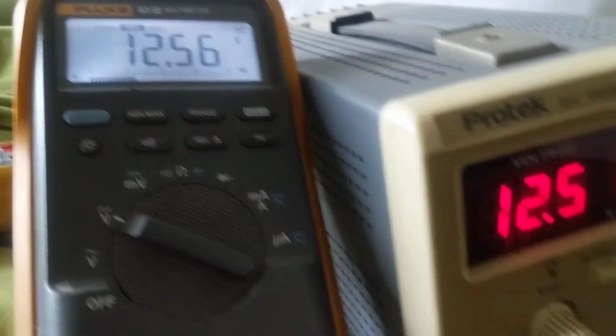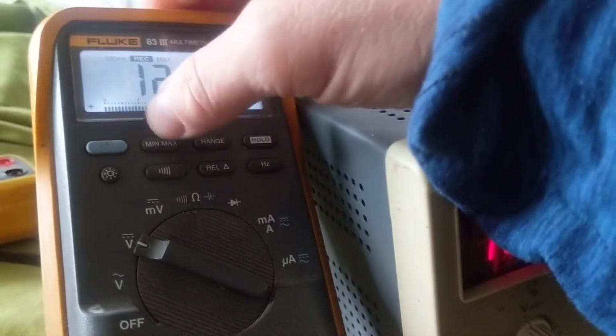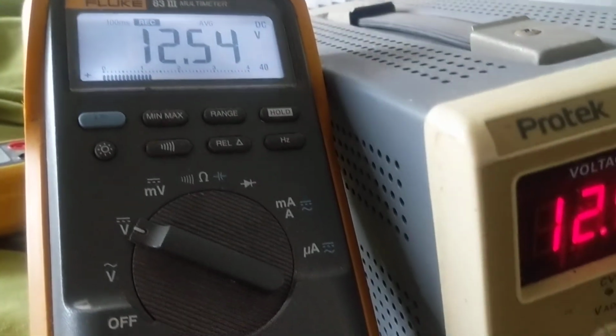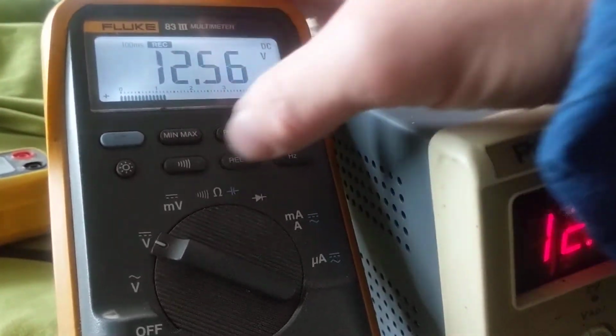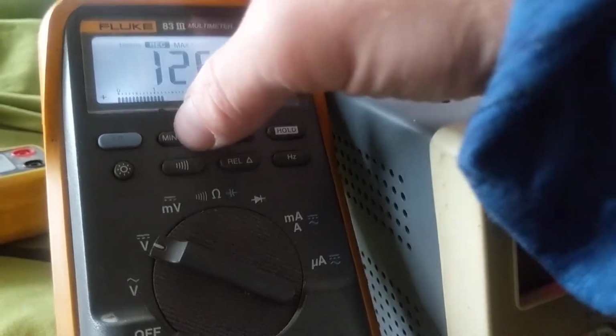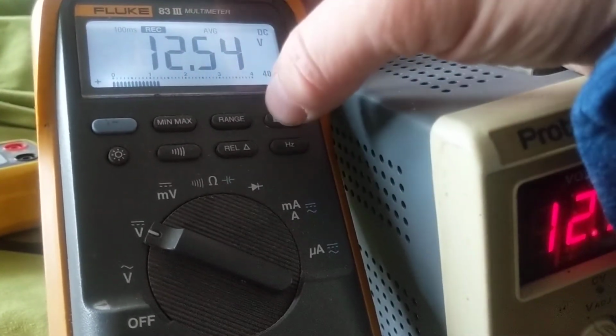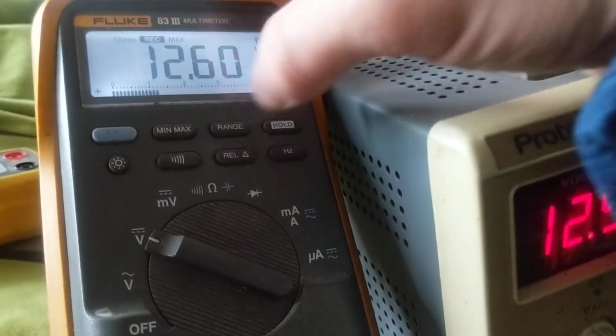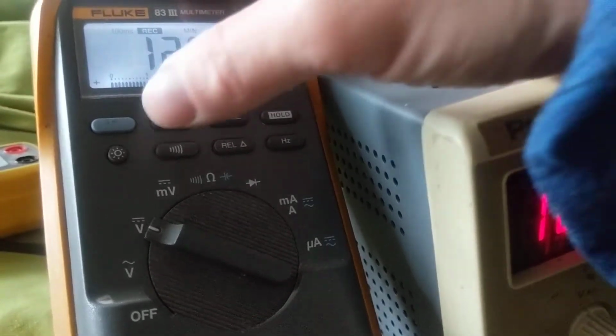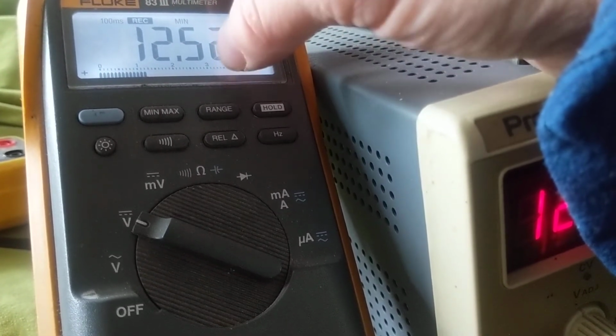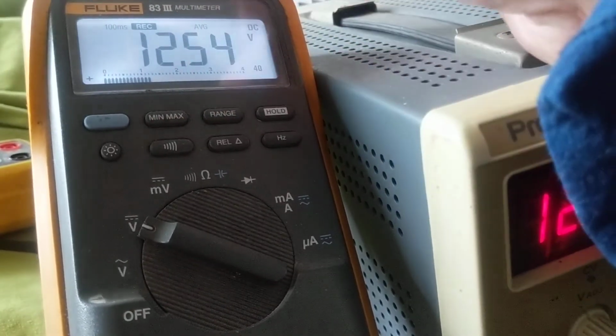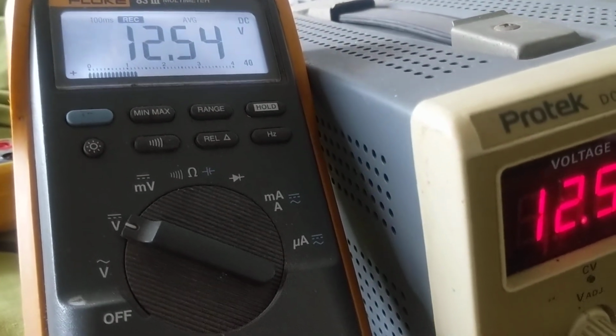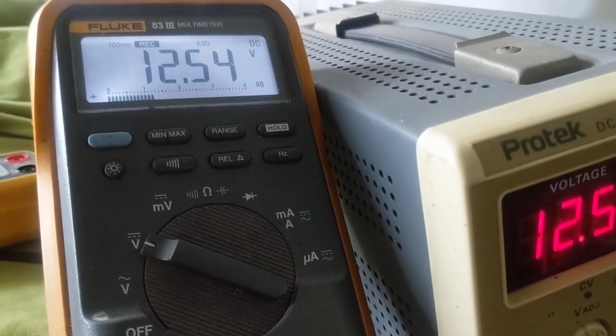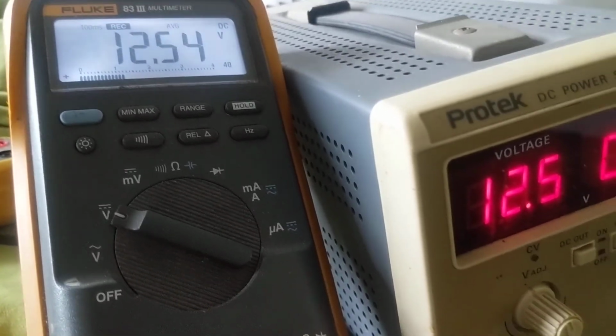There's something called minimum-max. Max means the maximum - if you press it again, that's the average, and then minimum. In this case, the maximum is 12.6, the minimum is 12.52, and it gives you the minimum voltage, the maximum voltage, and what I like, the average. So the average between 12.6 and 12.52 is 12.54. You don't have to worry about the numbers jumping up and down - you can take the average or the minimum.